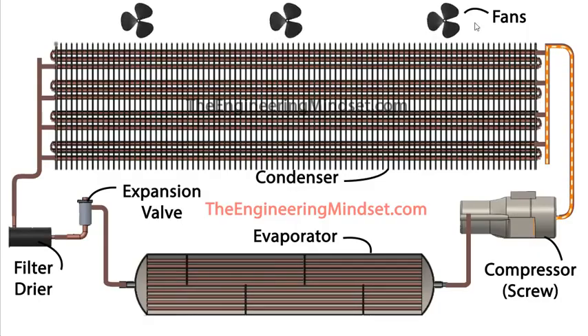And then we've got the condenser cooling fans, so these will be rotating, and that will be pulling the cooler ambient air across these coils. Remember here we've got the flow and return. It makes its way all the way throughout the loop. Have a look at that as well in just a second. So it's going to pull the air across that and extract all the heat away from the surface of this pipe. These fins in between are incredibly thin, and they're very easy to damage as well, so be careful if you're working or touching these.